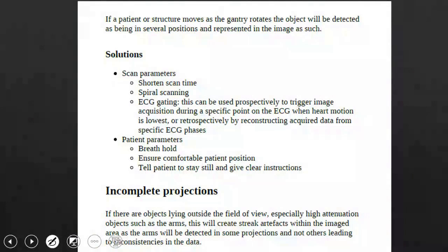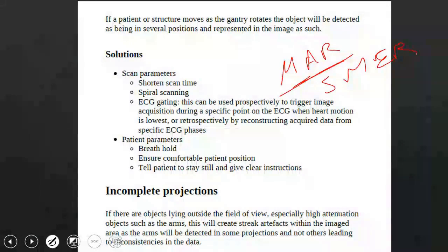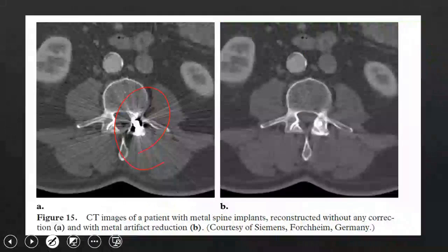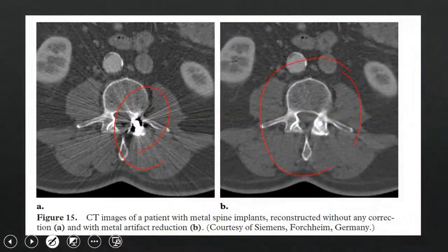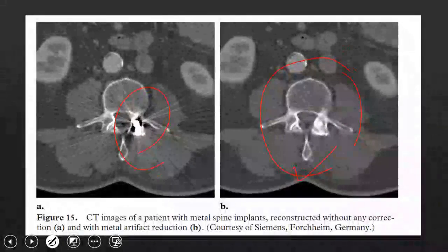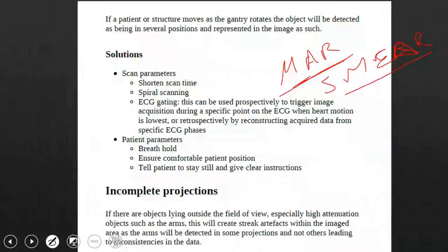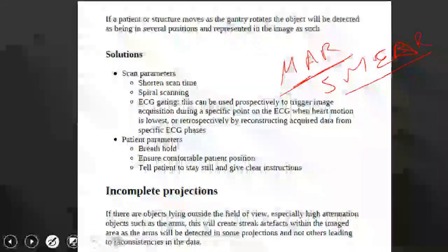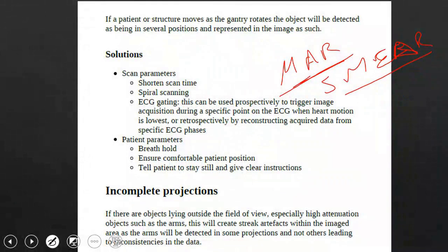Of course, there are tools used to treat metal artifacts, which are called metal artifact reduction software, and there is also one from Siemens. These are available today, and you can reduce the artifacts as you see. This is an image after applying it, where the artifacts completely disappear. As we see, this is the available technique, and the artifacts disappear entirely. Of course, this software is available on devices whether they are Philips, Siemens, GE, or others.